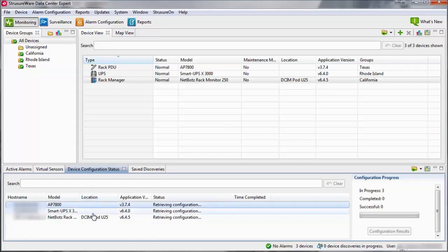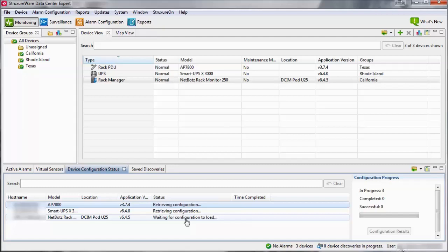You can monitor the progress of the configurations using the Device Configuration Status pane. Note that not all devices will be configured at the same time. Data Center Expert will start by retrieving the configuration from the device. The configuration changes will then be transferred to the device using either FTP or SCP depending on your device file transfer settings. The device will then have to process the changes. Data Center Expert then attempts to verify all of the configuration changes. Note that a configuration status of Incomplete does not mean that the configuration change did not occur. Right-click on the configuration status and select Show Configuration Results.